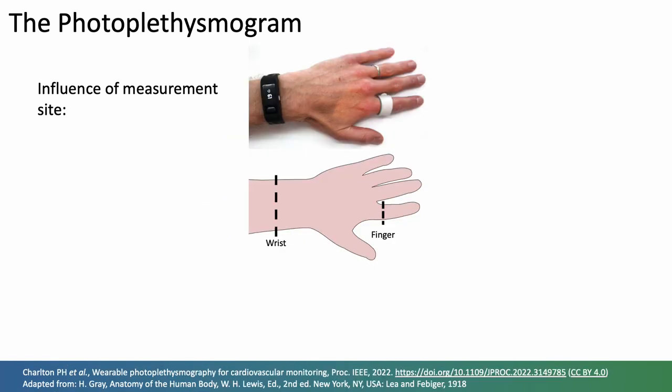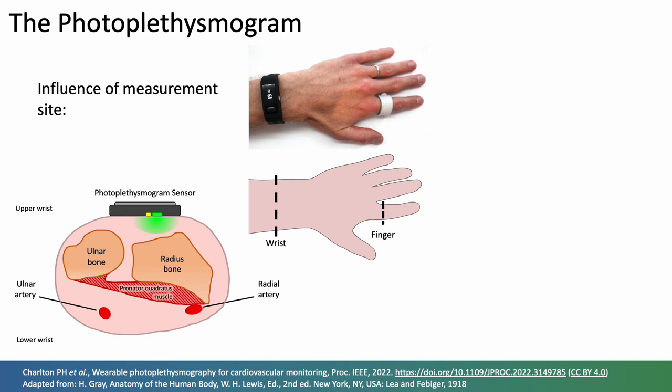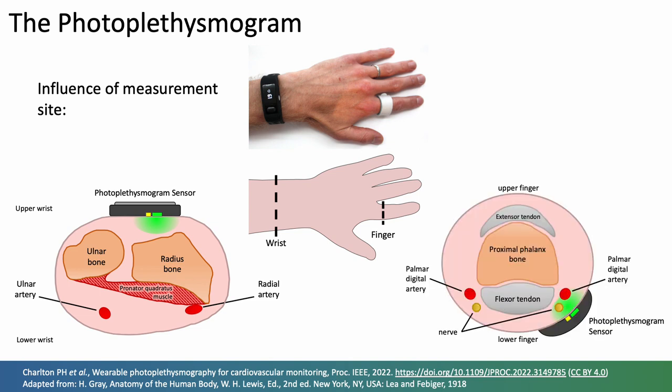The shape of the pulse wave varies between different measurement sites, so for instance comparing the wrist to the finger. Here is a cross section through the wrist where it's clear that a sensor mounted on the upper side of the wrist is situated a long way from the major arteries on the lower side of the wrist, so it probably primarily measures microvascular blood flow, whereas a sensor at the finger can be mounted very close to the main arteries of the finger, so it could be influenced more strongly by arterial blood flow.